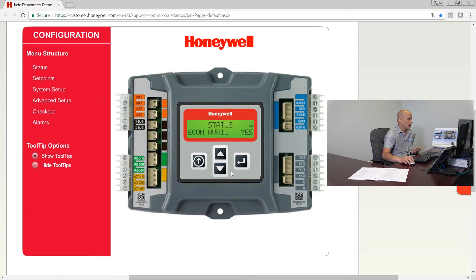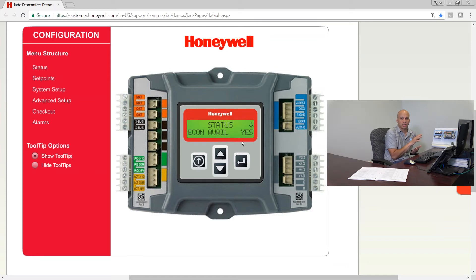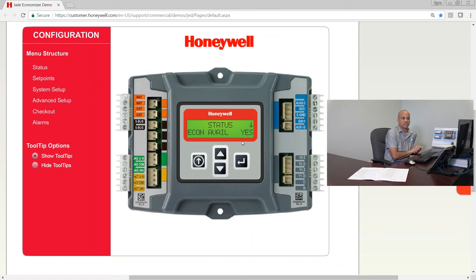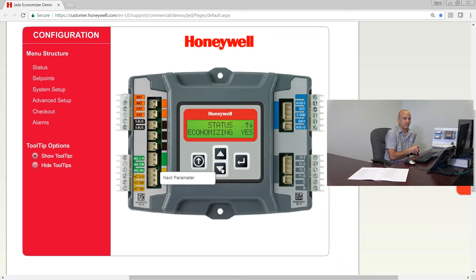Under status, when I click enter, I'll see the different things available to me. The entire status menu is not editable — this is a view-only thing; it's telling you what's happening right now at this moment in time. Settings and set points are where I tweak things; here is where I can see what's going on. The very first item is 'economizer available' — is it actually an economizer situation? Meaning, is the outdoor air cool enough, or if I have enthalpy, is it cool and dry enough to be an economizer day? It's just going to say yes or no.